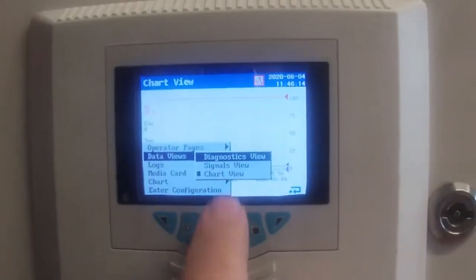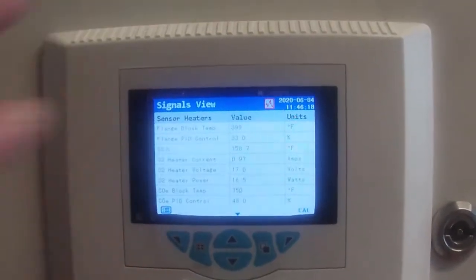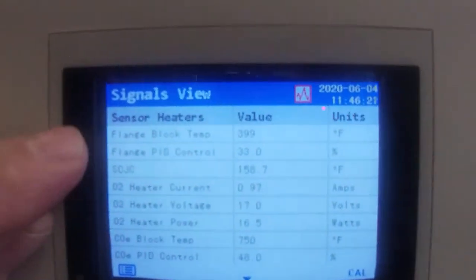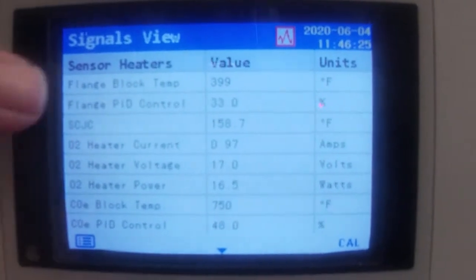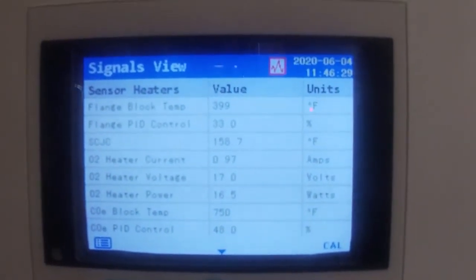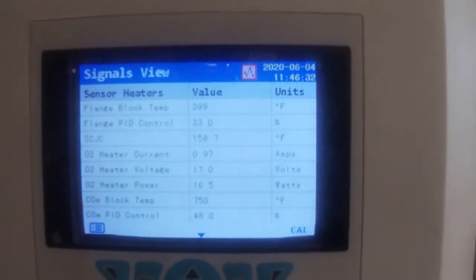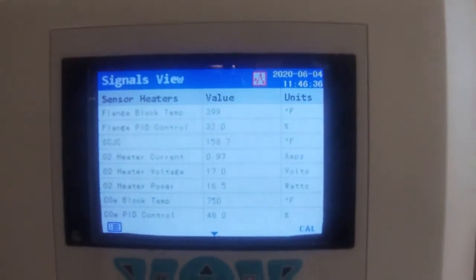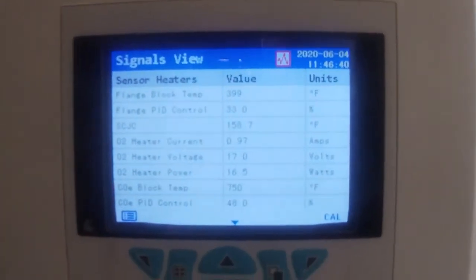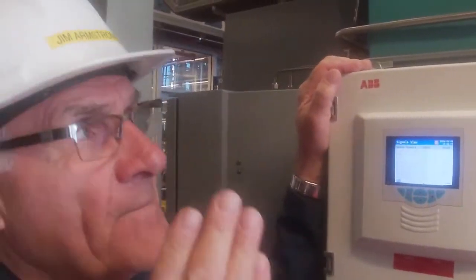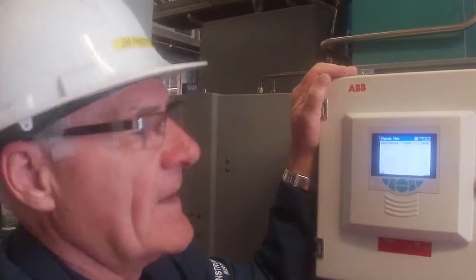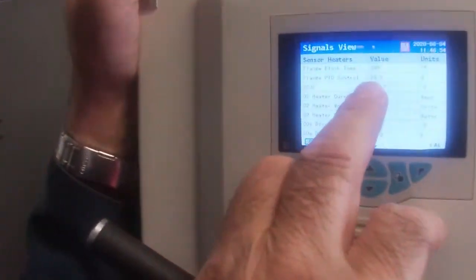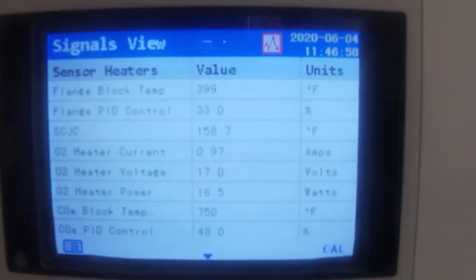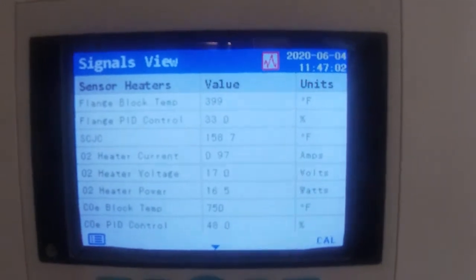I'm going to go back. I'm going to look at data views, and this time I want to look at the signals. Now, he's got 4 pages of this data, and it's actually showing me that the flange block, that is the main block up there, is running at 399 degrees. It should be 400 degrees plus or minus 5 degrees, so we're well within spec. It actually uses a PID control algorithm to control the heaters. There's 4 heaters inside there, and it's actually using a pulse width modulation signal onto those heaters to control the temperature. And right now it's running at 33% of its rate. So basically 33% on time, 66% off time to maintain the temperature.